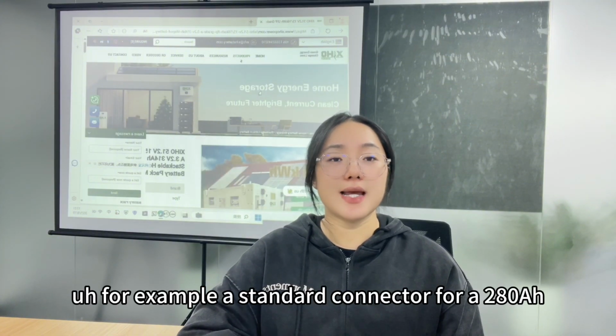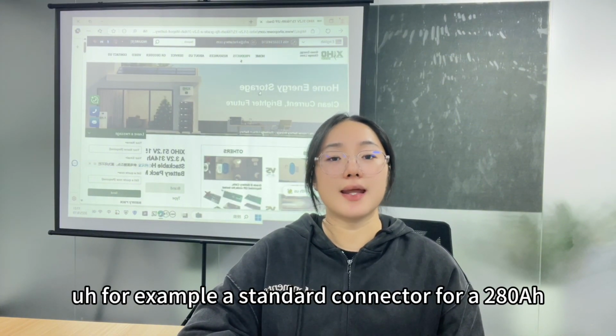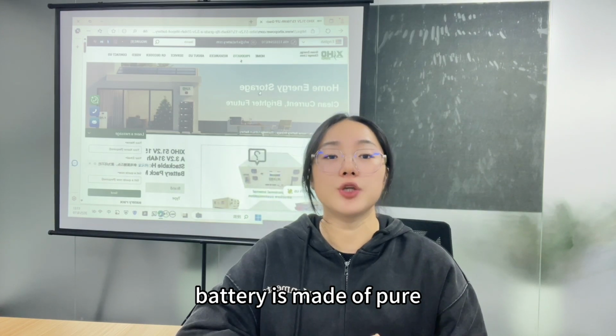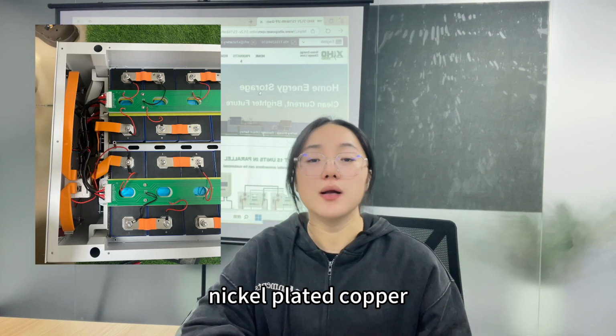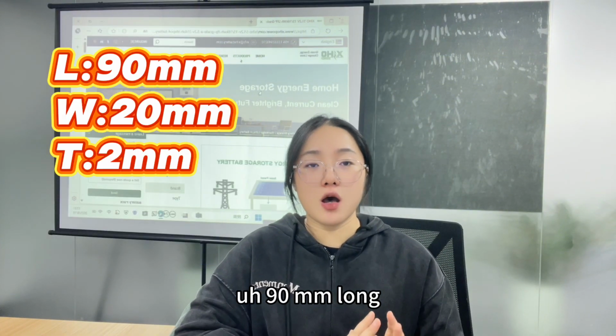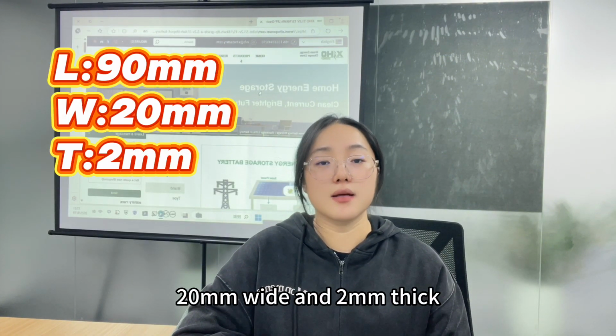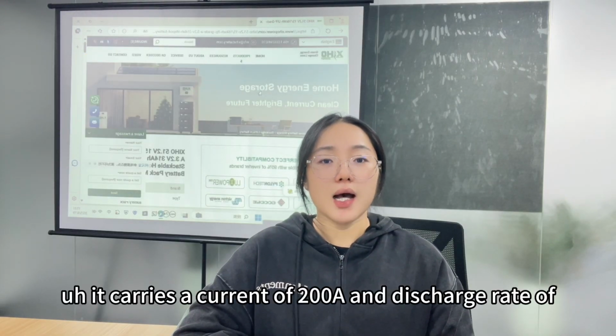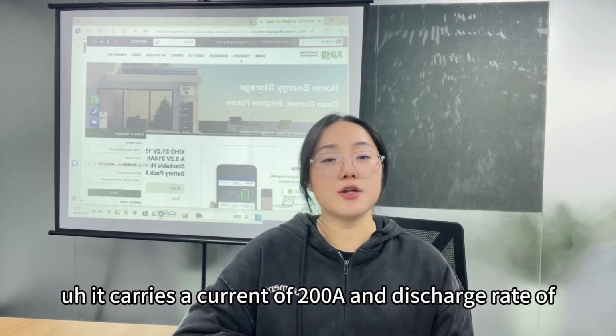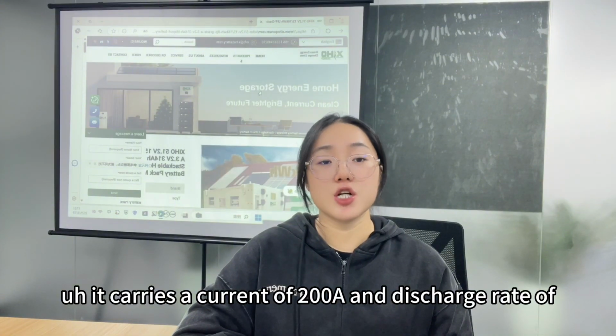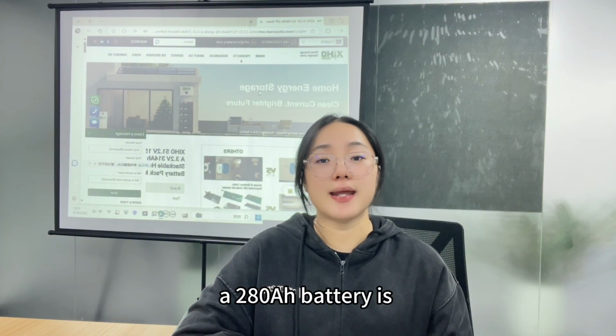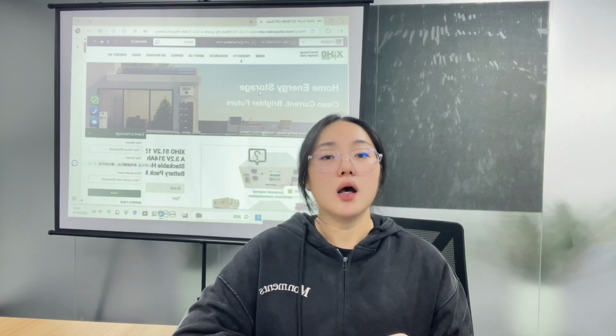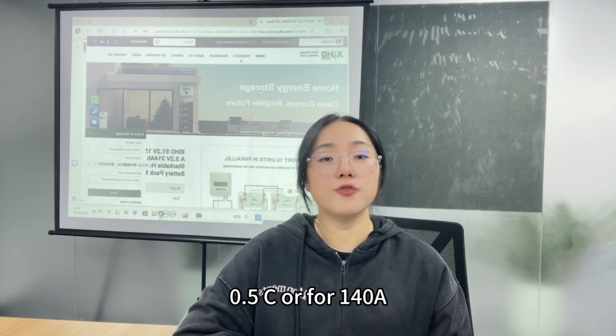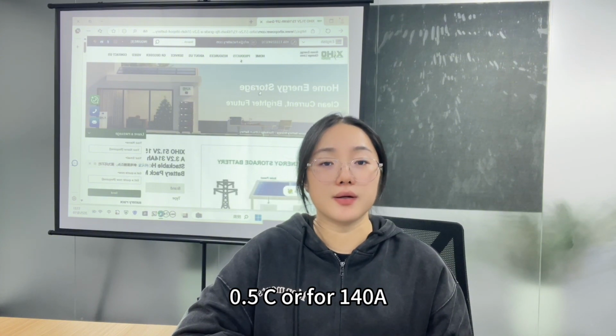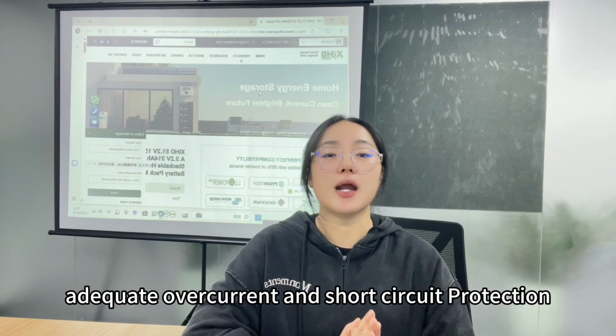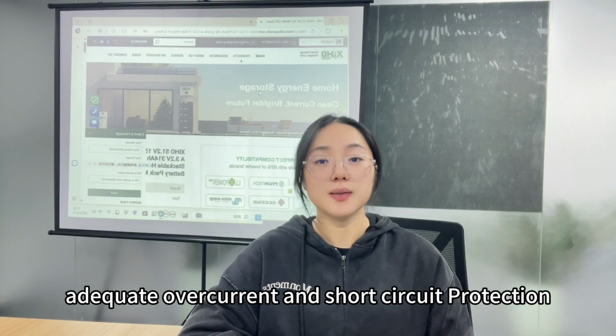For example, a standard connector for a 280 amp-hour battery is made of pure nickel-plated copper, 90 millimeters long, 20 millimeters wide, and 2 millimeters thick. It carries a current of 200 amperes, and the discharge rate of a 280 amp-hour battery is 0.5C, or 140 amperes. It has adequate overcurrent and short circuit protection.